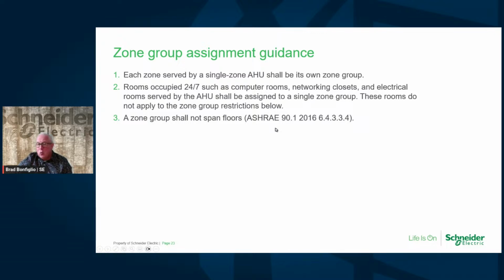Zone groups shouldn't span floors. You shouldn't have one VAV box on a floor with an air handler and then try to sync up or link a zone on another floor. Obviously, that doesn't make sense. Each one needs to be dedicated, because you're resetting the static pressure and the temperature, and you obviously want to do it on the air handler affected by the units that are serving it.